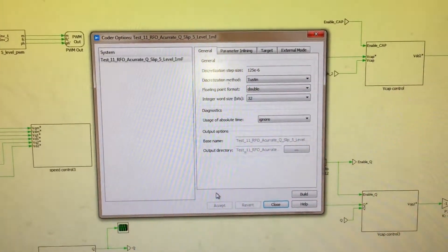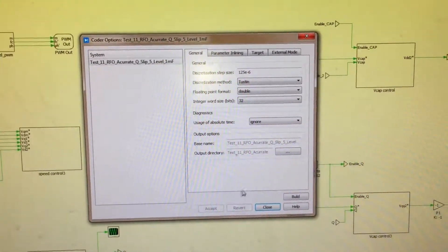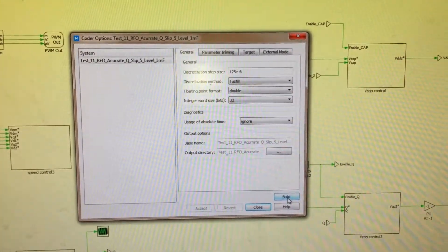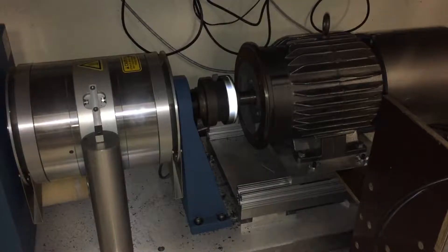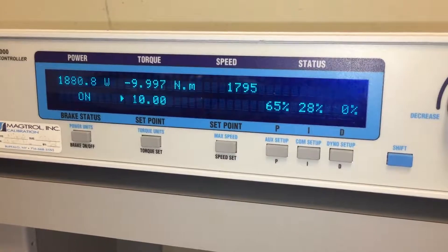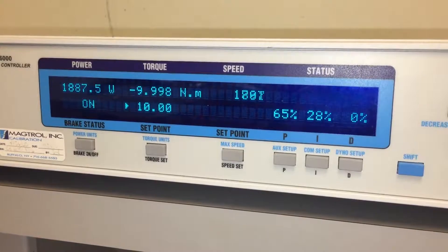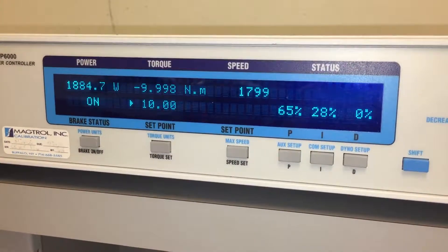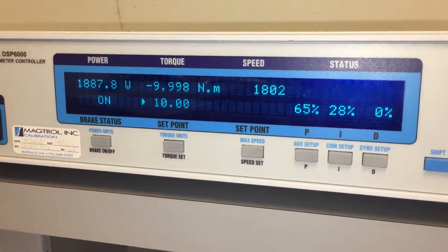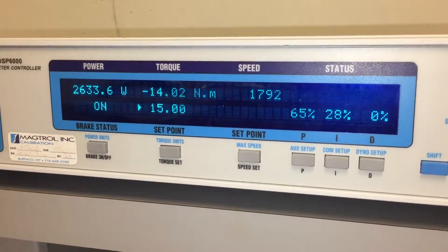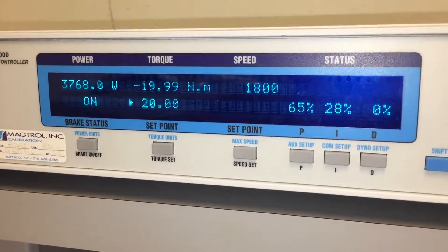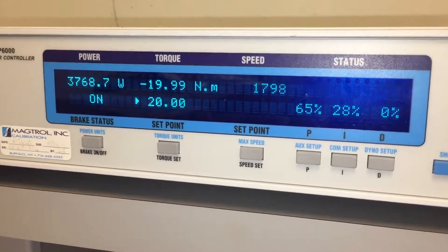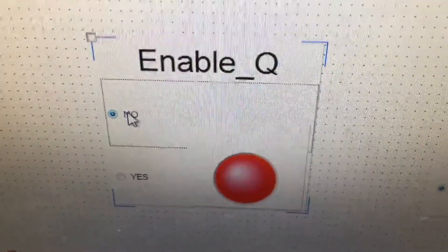I have now turned on the blower, so there is background noise. I'm going to run the motor by clicking this button so the code will be built and sent to the controller — watch the rotor carefully. The motor is now running at full speed with half load, generating 1.88 kilowatts of mechanical output. I will now increase the load torque. The motor is running at full speed 1800 rpm with full load of 20 Nm and generating 3.76 kilowatts of mechanical power.